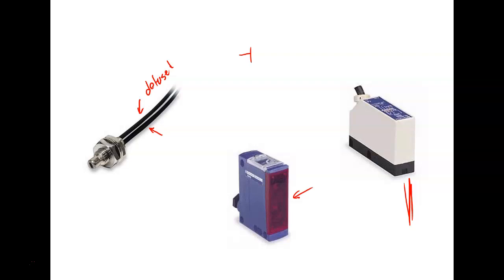On a through the beam, we'll put out two fiber optic cables, and the two sensors will be mounted on both sides. We have two types of fiber optic cables, glass or plastic. In industry, the most popular is plastic, because all we're doing is sending trues and falses.